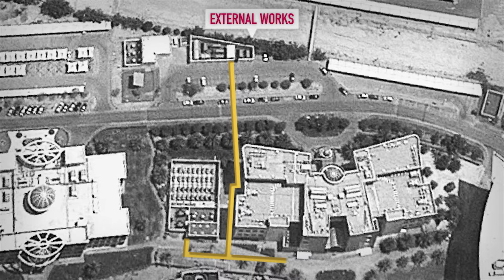External works. Project works will start with 2 new trenches that will be excavated, one running from the Generator's site to the new Electrical Room 2, and the other running from the Transformer's compound to the new Electrical Room 2. PVC ducts will be laid down in the trenches to allow new power wires for both the new utility and Generator's power source branch number 2.